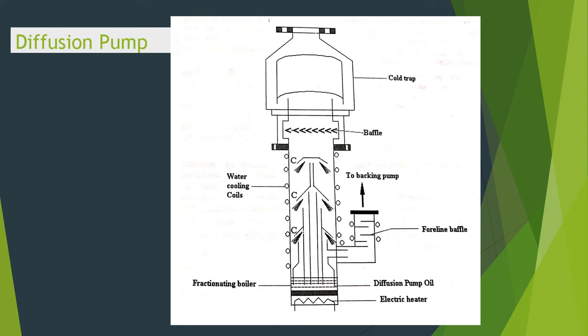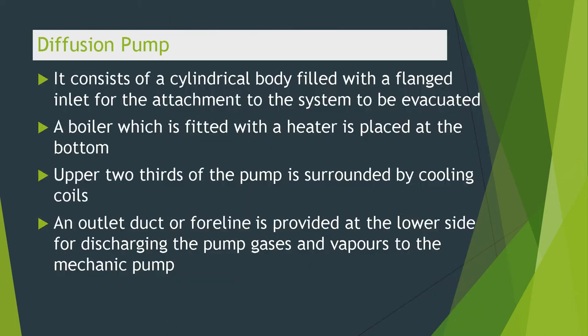This is the overall figure of a diffusion pump. It consists of a cylindrical body with a flanged inlet for attachment to the system to be evacuated. A boiler fitted with a heater is placed at the bottom. The upper two-thirds of the pump is surrounded by cooling coils. An outlet or fore line is provided at the lower side for discharging pump gases and vapors to the mechanical pump.